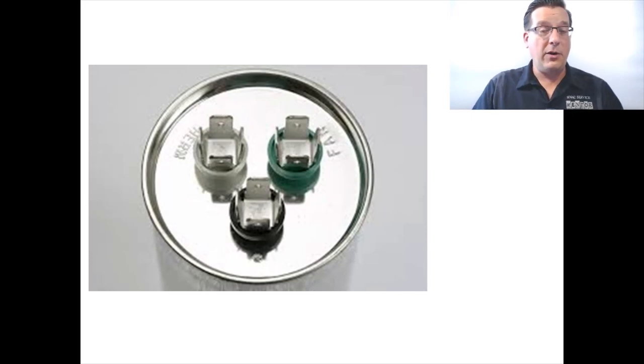Here's an example of a dual run capacitor with the C terminal in black at the bottom, the fan terminal in green on the right, and the HERM terminal in white on the left. So just imagine that from here to here is the five microfarad capacitor, and from here to here is the 35 microfarad capacitor. And of course, dual run capacitors come in all different sizes and values. 35-5, 25-5, five is real common, sometimes seven and a half, right? 55-7 and a half, 85-5, all types of different values. But what we're talking about is one device that actually has two devices inside of it.